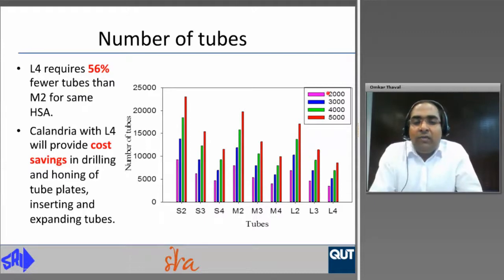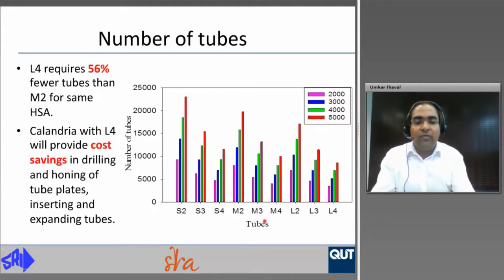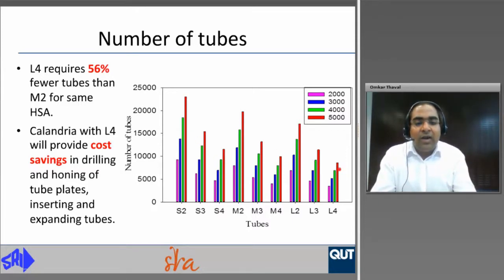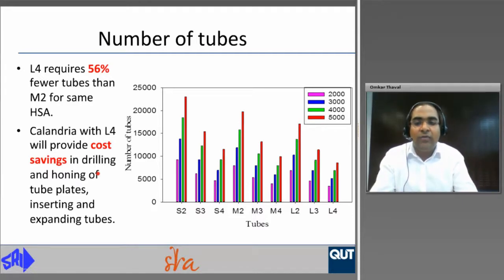Once the model was developed, we looked at the different outputs. For the number of tubes, it is seen that the large diameter and 4 meter tube has 56 percent fewer tubes for the same heating surface area. Calendrias with large diameter and 4 meter tubes will provide cost savings in drilling and honing of tube plates and in inserting and expanding tubes.